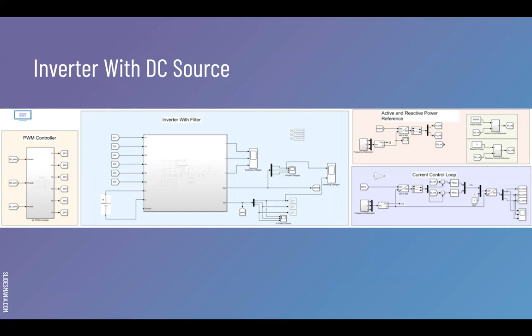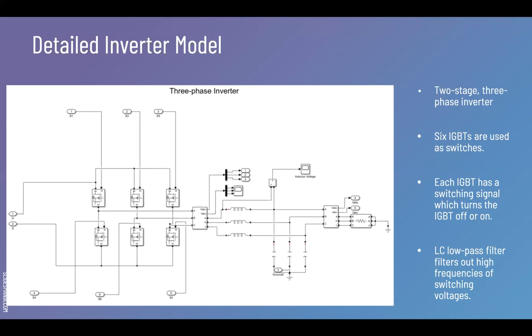So if you look here, this is the detailed model of the inverter itself. As you'll notice, it's comprised of 6 IGBTs, which function basically as switches. Each one of these has an input signal that's coming from the PWM controller. And the other 2 inputs you see on the far left are the DC input. Right now, this represents a simple DC input, but eventually it will be connected with the PV system. In addition, you'll also notice a capacitor and inductor on each one of these phases. What that does is it acts as a low pass filter, filtering out any high frequencies from the switching voltages in order to get a smooth three-phase AC at the output. Next.